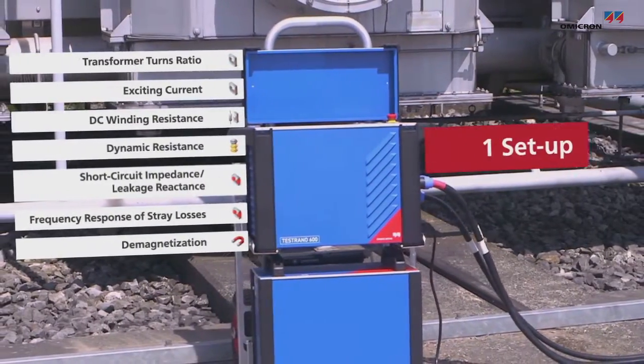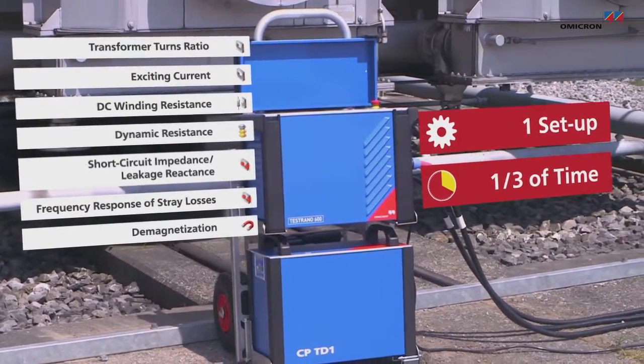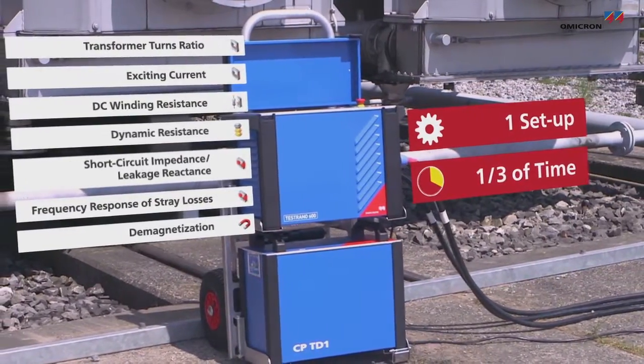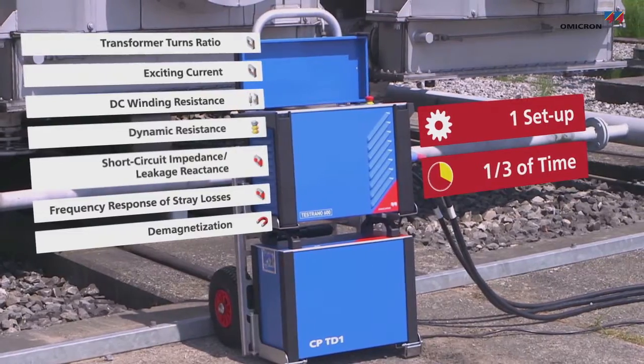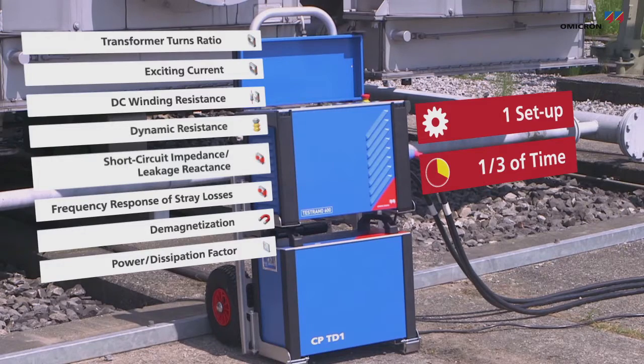All of this can be done with one setup, cutting testing time down to a third of what it was with conventional single-phase test sets. Together with the CP TD1 you can also measure power factor or dissipation factor and capacitance.